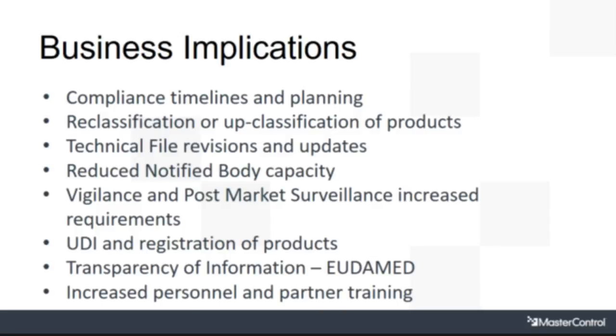There's going to be a staged implementation of the UDI requirements, and it's an area that every company is going to have to take a look at and see what they need to do to comply. And we have some significant experience from working with clients for the US, so we're available to help out there. EUDAMED will be the database where information about devices will be stored, just like in the US under the Global Unique Device Identification Database. So there will be information in there about all those devices on the marketplace. And there will be a lot of increased training requirements.